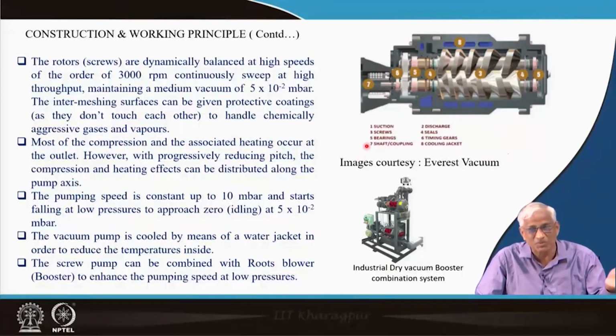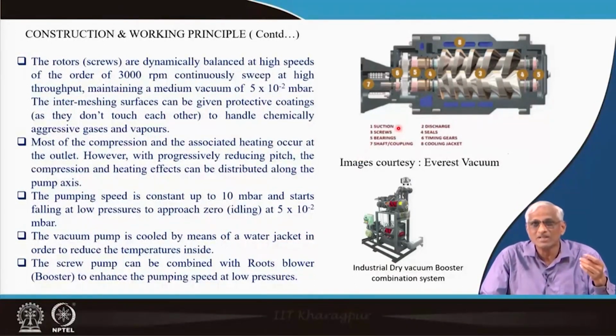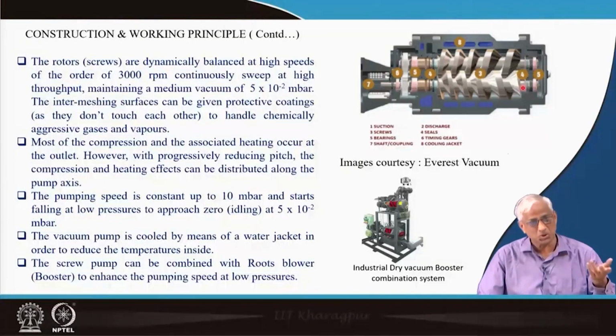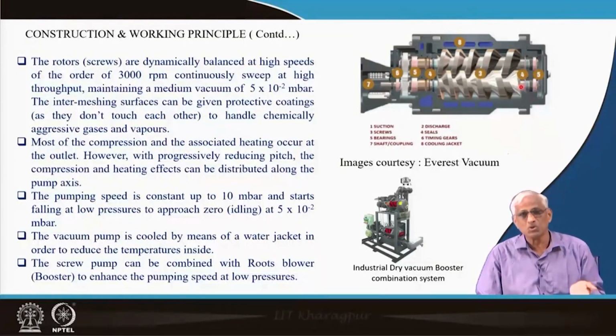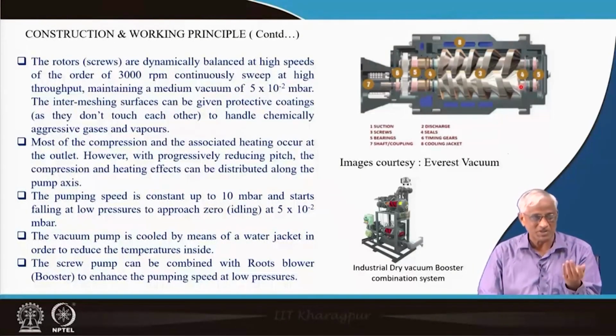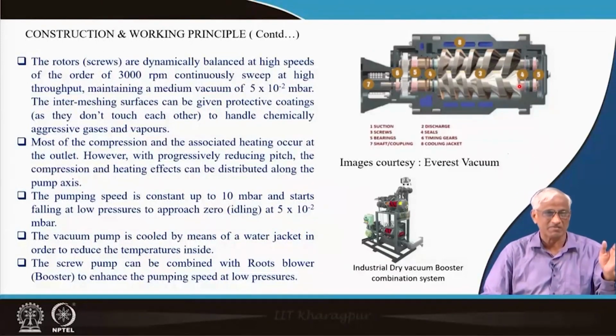We have seen already in rotary pumps, diffusion pumps, etc., the same thing here. In fact, most pumps up to 10 millibar have fairly good pumping speed. Afterwards, they start falling, and around 0.1 they almost approach zero. You can use booster pumps, roots blower, to boost the pumping speed at lower pressures and also to get a little better vacuum.